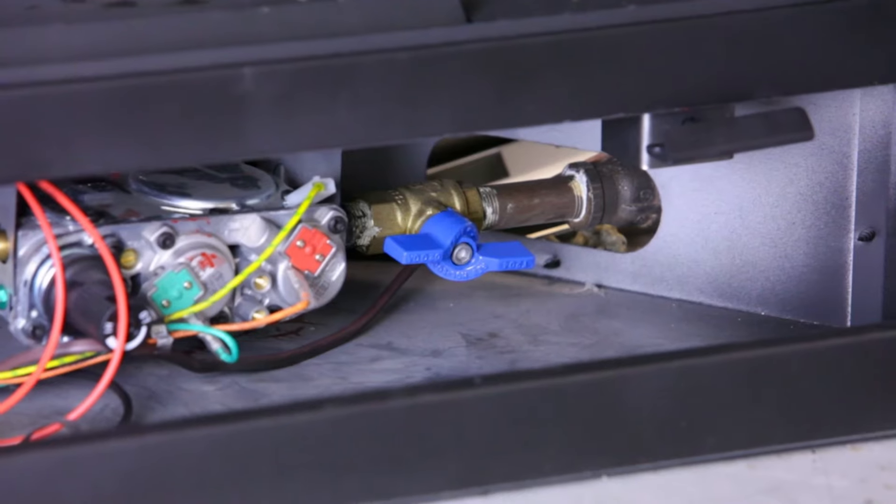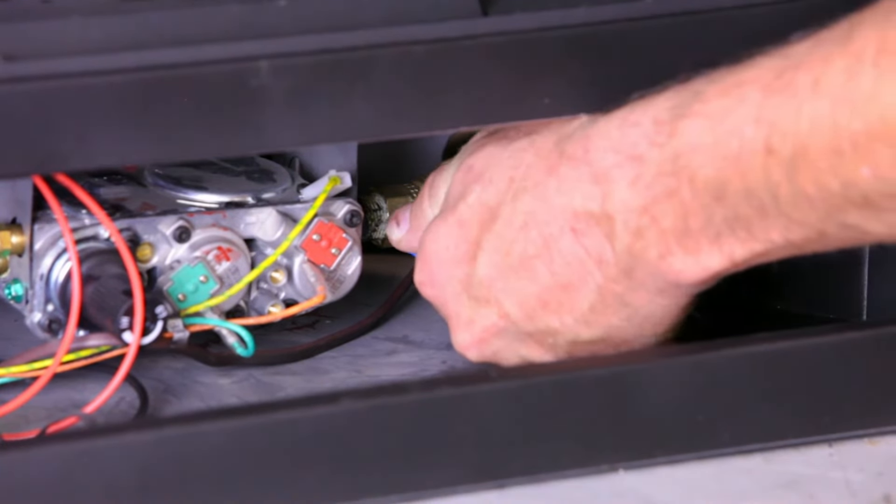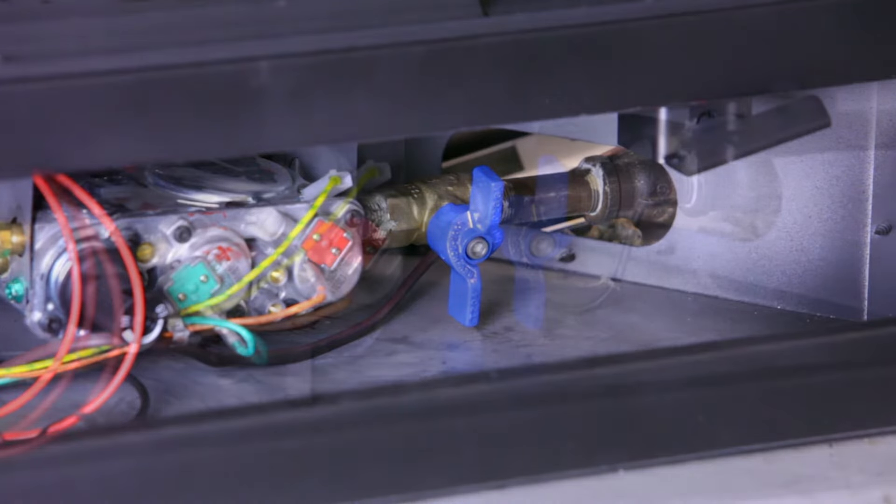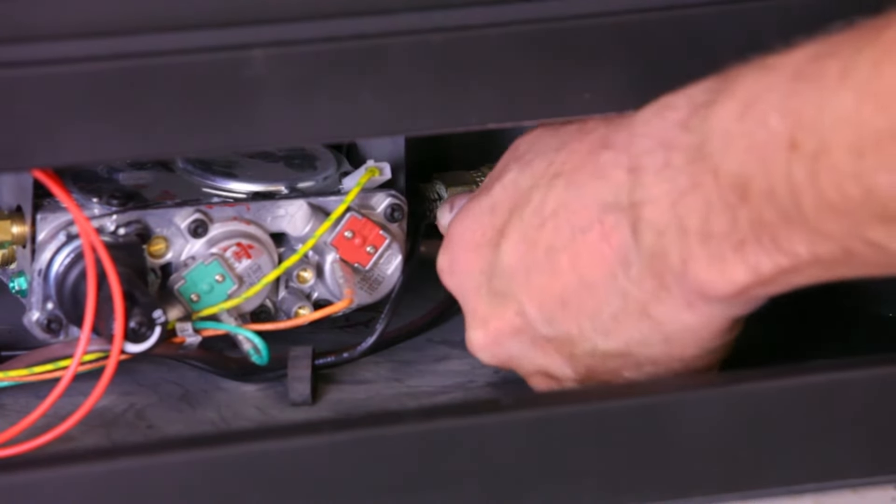If the electrode is sparking to the pilot hood but there is no flame, then check if a manual gas shutoff valve is open. The gas valve may be concealed. The manual gas shutoff valve is closed when the handle is perpendicular to the gas line and open when the handle is in line or straight with the piping.